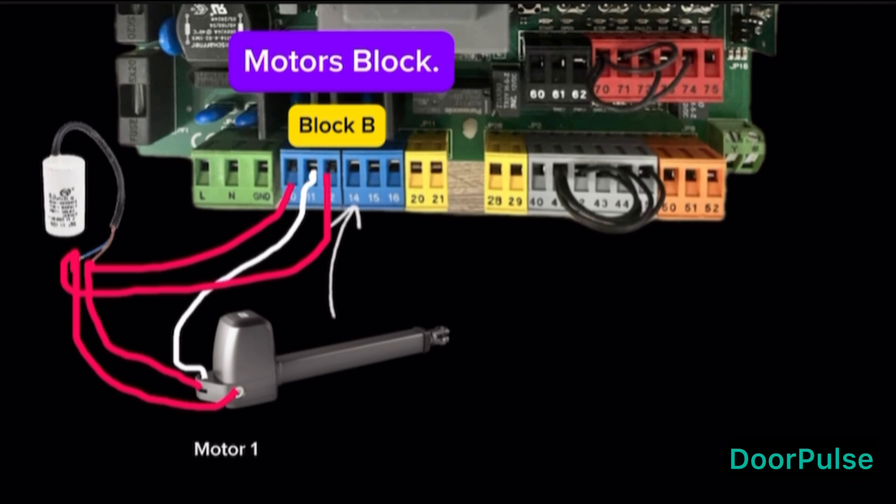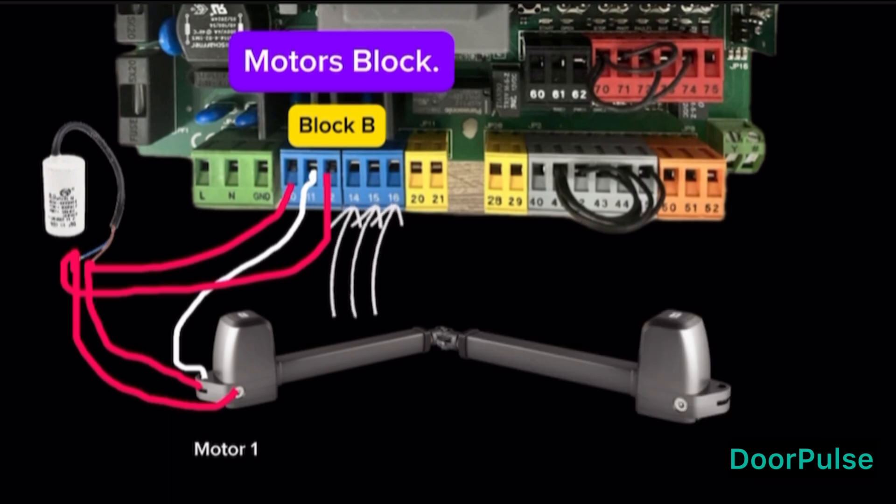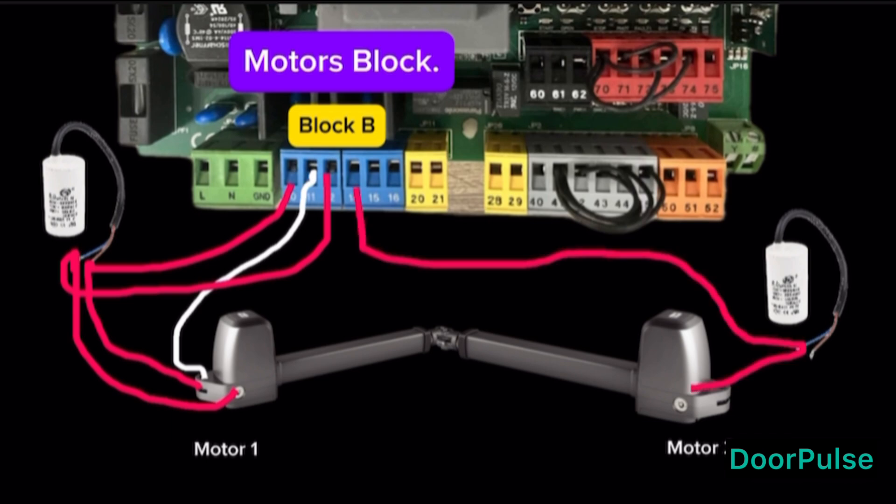Terminals 14, 15, and 16 is Motor 2. Terminal 14, connect Motor 2 phase wire with condenser. Terminal 15, connect Motor 2 common wire only. Terminal 16, connect Motor 2 phase wire with condenser.